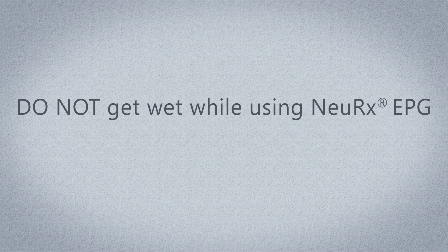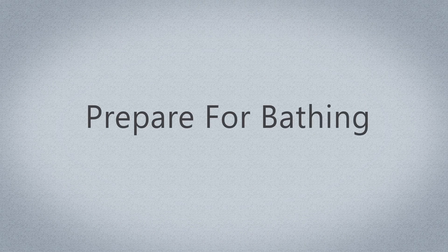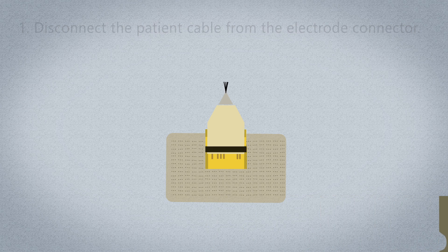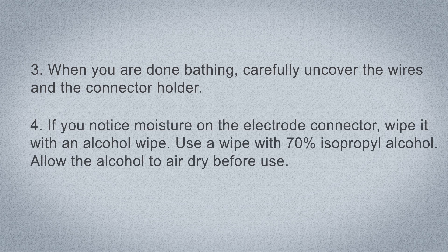How to shower or bathe. Do not get wet while using the NeuRx EPG — this includes bathing, showering, or swimming, as the NeuRx EPG is not waterproof. Before bathing, disconnect the patient cable from the electrode connector. Cover the wires and the connector holder with a waterproof dressing. When you are done bathing, carefully uncover the wires and connector holder. If you notice moisture on the electrode connector, wipe it with an alcohol wipe with 70% isopropyl alcohol and allow it to air dry before use.